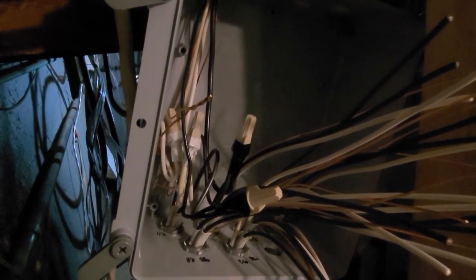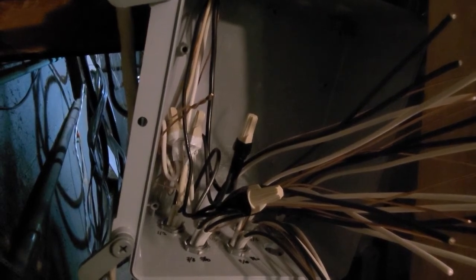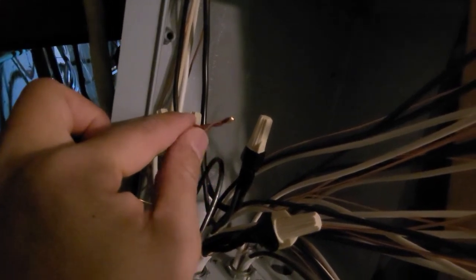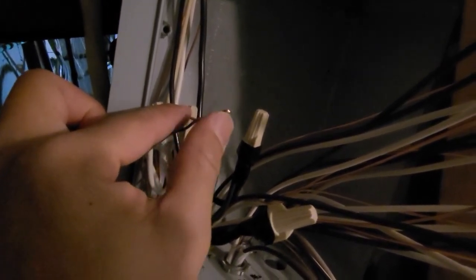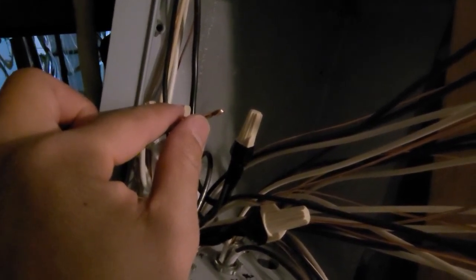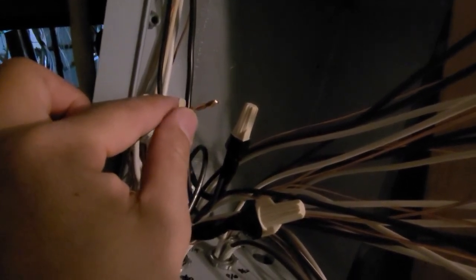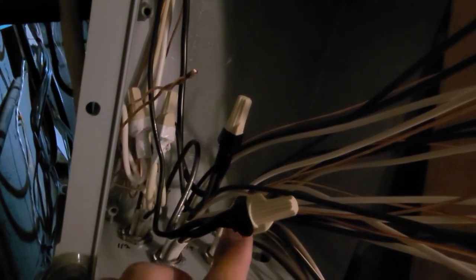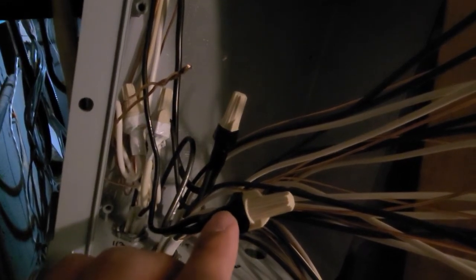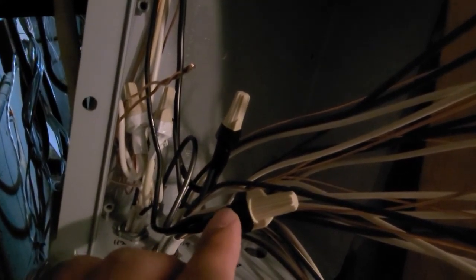You can see I connected the first 2 wires together to the new panel, and when you twist the 2 wires together, always make sure it's a good connection, especially when the 2 wires are not the same gauge. You have to make sure you have a good twist. Otherwise, when you put the marrettes on, the bigger wire will try to push the smaller one out. So that's why I always put some electrical tape here, not only to make sure of a good connection and no exposed wire, but also to make sure the wire does not come out of the marrette.